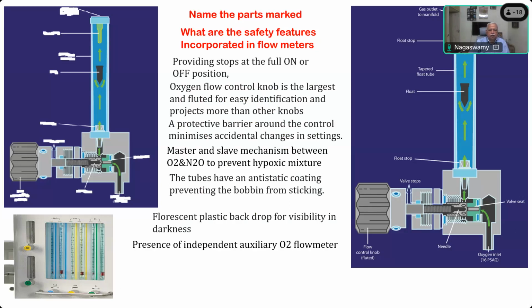Presence of independent auxiliary oxygen flow meter. This is a very important newer feature added in all the anesthesia machines. So even if the main flow meter fails, you can still have oxygen delivery through this. And downstream placement of oxygen flow tubes to prevent hypoxic mixture. So these are all the points that you have to remember for the safety features incorporated in flow meter.